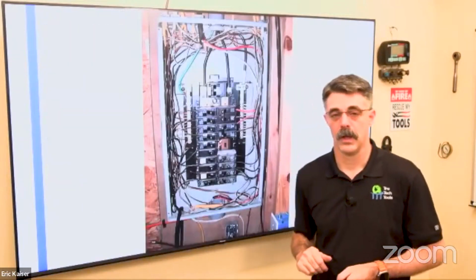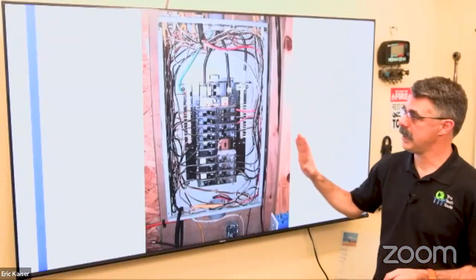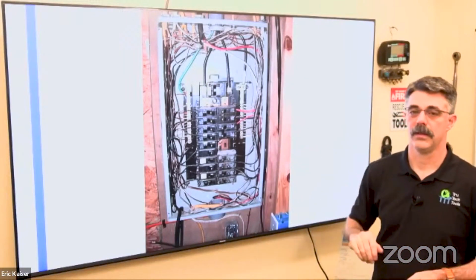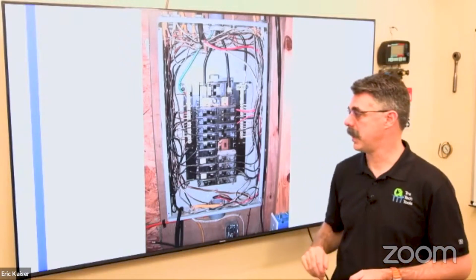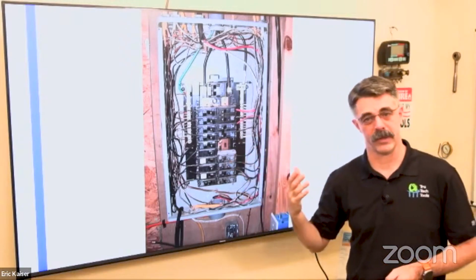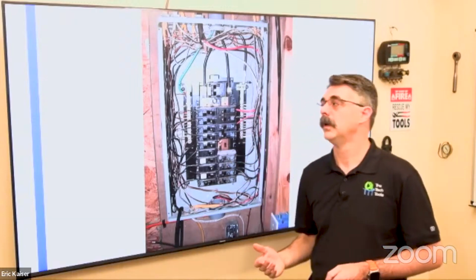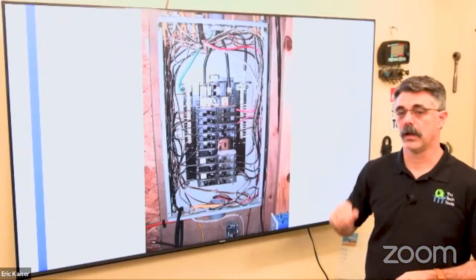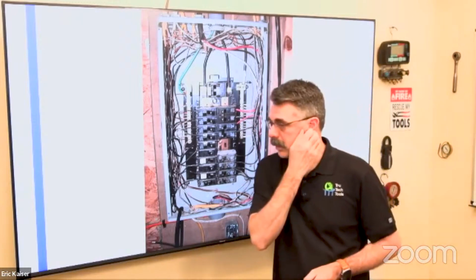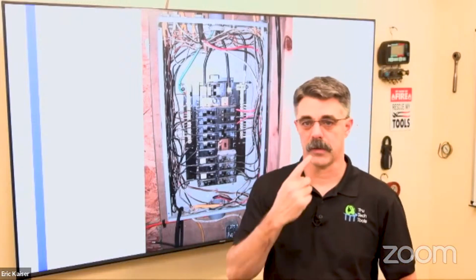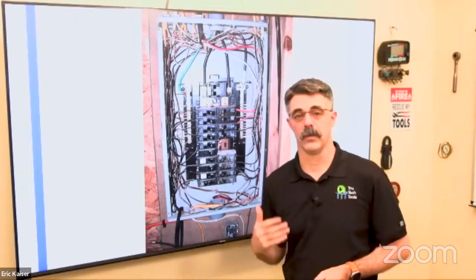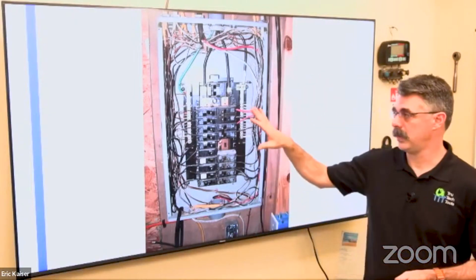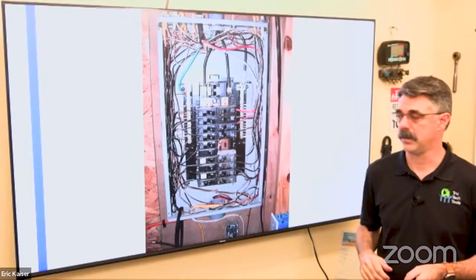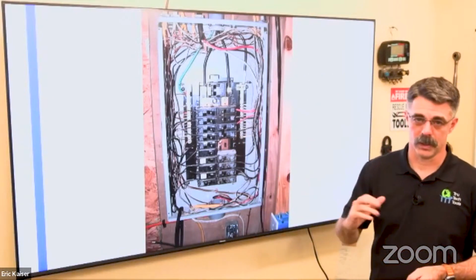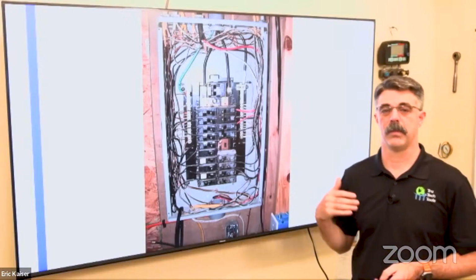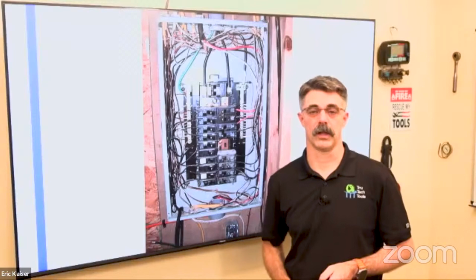Okay? If we're going to go all electric, we need to take a close look at the electrical panel. Right? We need to make sure that there's physical space in there because we may be having extra breakers added. So make sure that there's enough space and/or enough capacity. Now, if you have things like 100 amp electrical service and you want to go all electric, there are load shedding options out there that will monitor the loads and help control them, turn them off and on whenever they need to, things like that. So look into those options. I don't know a whole lot about them, but I have read about them and I've seen people demonstrate them. They look like they might work pretty well.